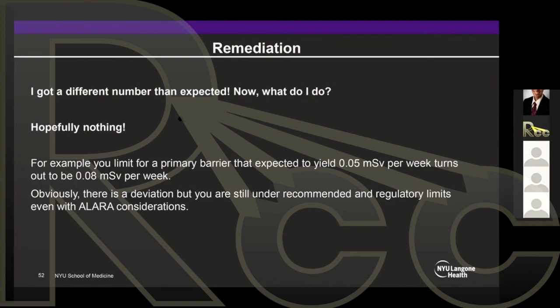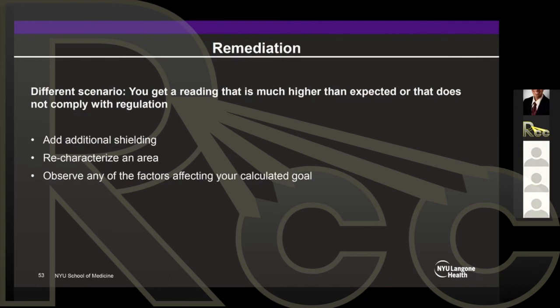Well, hopefully nothing. For example, if for a primary barrier you expected to get 0.05 millisievert per week, and it turns out to be 0.08, well, obviously there is a deviation, but you're still under recommended and regulatory limits, even with ALARA considerations. So it's fine. You're actually meeting everything you wanted to meet. It might be a small deviation, but that's it. Different scenario: you get a reading that is much higher than expected or that does not comply with regulations.